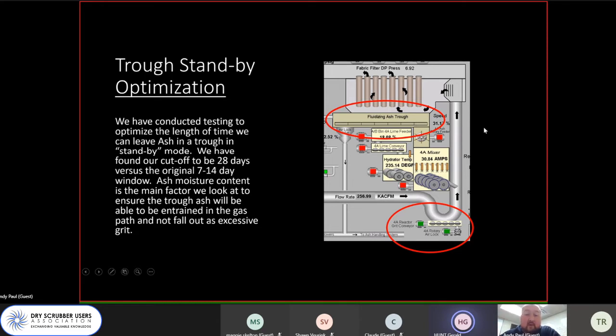So it'd be Unit 4 ash, and typically in a year we'll have to clean out a trough. It depends—we've had more instances with higher bag failure rates, because sometimes we'd have to drop the bag down into the trough, and to retrieve it you have to either fully or half empty the fluidizing trough. That's part of the reason we came up with this idea, to pull ash out of our silo and put it in there. We were experiencing a lot of times where we'd have to refill the trough. Under normal operation, without a high bag failure rate, we probably have to refill a trough maybe once a year, typically during our longer outage of the year.